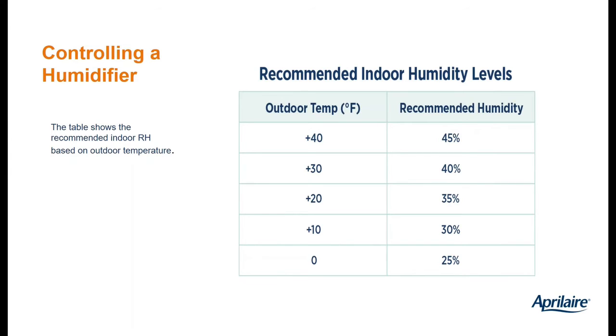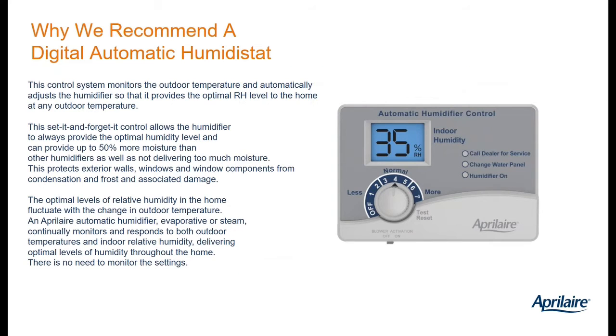So you can see the water on the windows. That's an indication that your relative humidity is too high, regardless of what the RH is. If it's 20 below zero, you're not going to be able to hold 35% in your house. That's one of the advantages of the automatic humidistat. So let's talk about that.